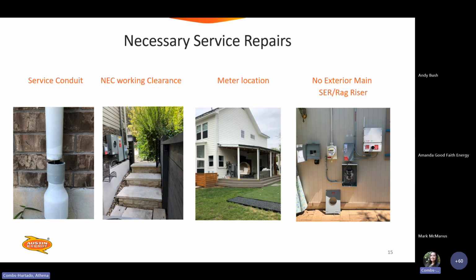All right, so necessary service repairs. So I said this in the last slide, but you will have to make sure to address any issues before installing. This will require an upgrade permit before the solar can start. So if the conduit is separated, if there's not enough clearance, you need 30-inch wide clearance. If the meter is in an enclosed area, you'll need to address the revenue meter. And then service riser, no main disconnect is an older service. So again, you just have to have that upgrade permit before the solar can start.